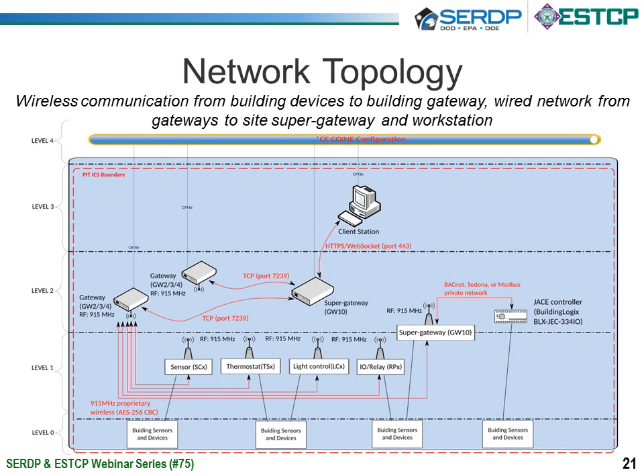Slide 21 is just a quick overview on the network topology. This is a wireless system, but it's really only wireless for the last leg. So in each of these buildings at a DOD facility, we install at least 1 or more gateways. You can see it here in level 2. These gateways have an Ethernet port, and they plug into the network, the local industrial control system network, or ICS network, at a base, and are able to communicate through that.